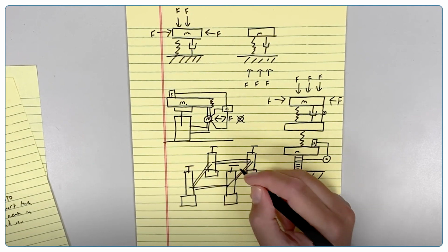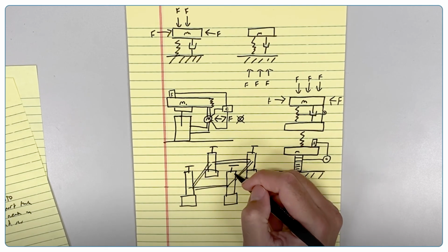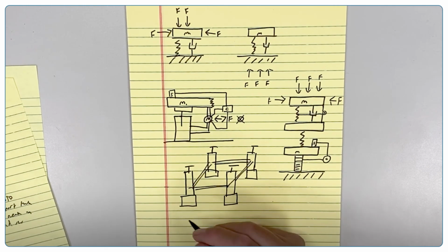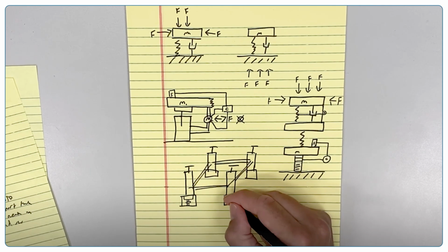Where your first stage of isolation is a pneumatic mass spring damping system, which may or may not have an additional electro-damp parallel type active cancellation system, supported by your second stage of isolation, which are the serial type piezo isolators I had mentioned before.